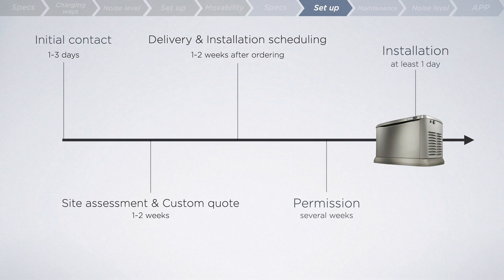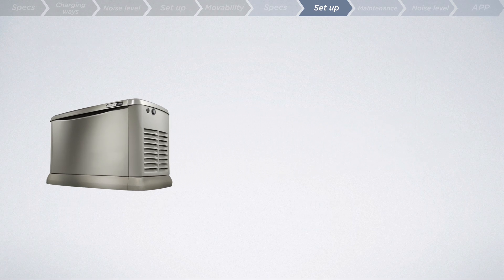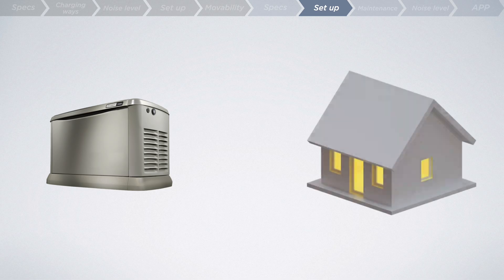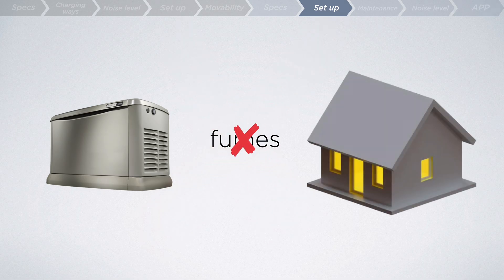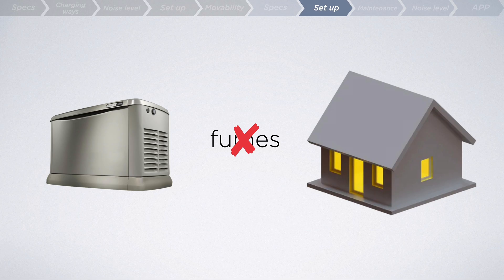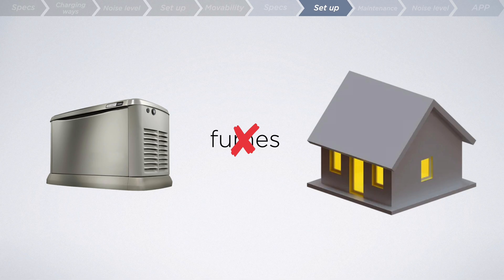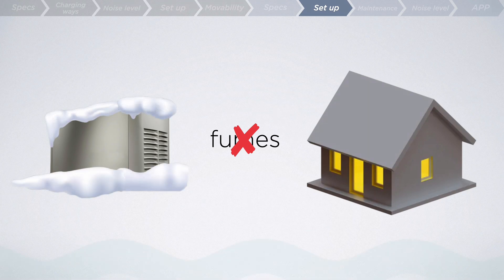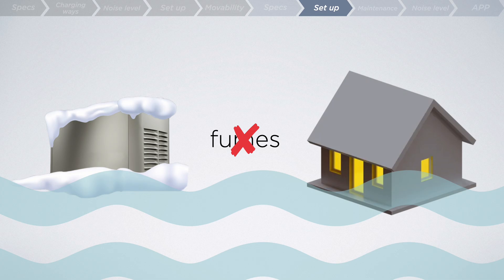Keep in mind that this type of generator can only be installed outside, considering the fumes they produce. However, this exposure also renders the generator vulnerable to extreme weather conditions like winter storms or hurricanes. If covered by heavy snow or flooded, the entire system can become inoperable, particularly if the air filter becomes clogged.